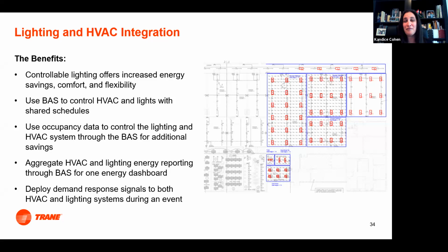Probably one of my favorite use cases is using occupancy sensor data to extend those energy savings further. Someone walks out of the space, ten minutes pass, no one else comes in, the lights shut off—but also, to Kenny's point, you can close that VAV damper so you're not conditioning an unoccupied space. There's tremendous savings from utilizing that, and it's very simple to do through integration.